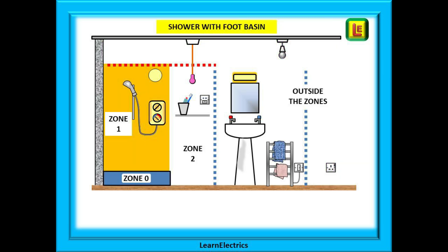Let's look at rooms with showers. These are essentially the same as bathrooms, with zones and outside zone areas. Zone 0 is the space inside the footbasin. Zone 1 is the space above the footbasin to a height of 2.25 metres from the floor, with a width equal to the outside edge of the footbasin. Zone 2 is 0.6 metres from the outside edge of the footbasin, and then we have the outside zone areas as before.